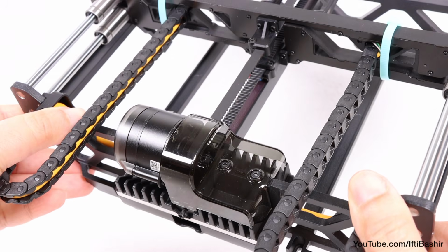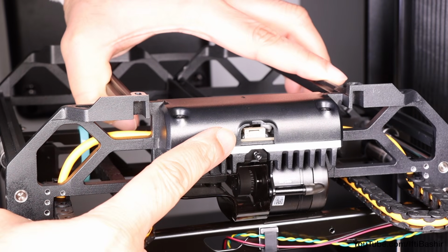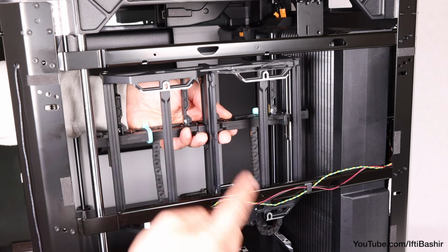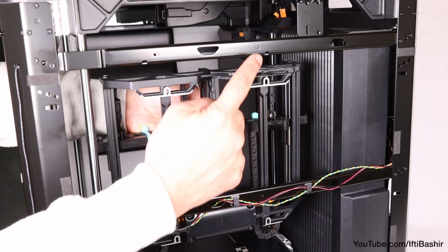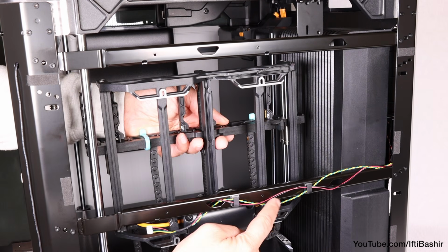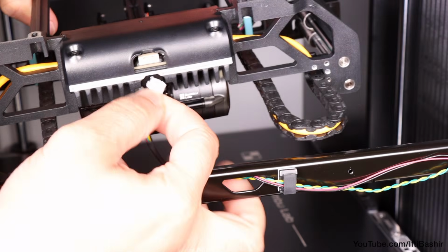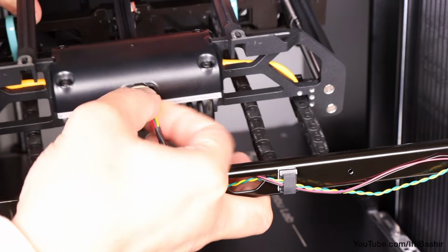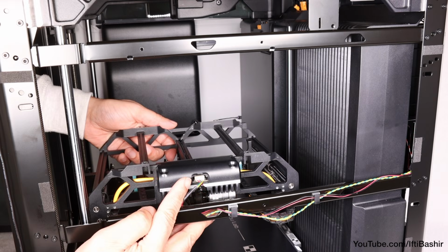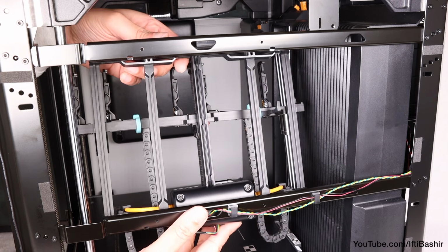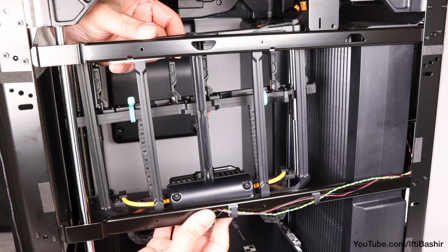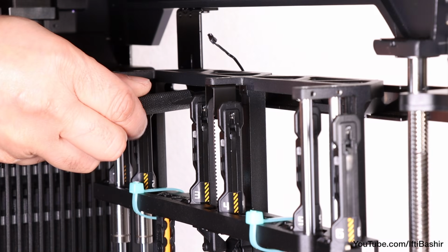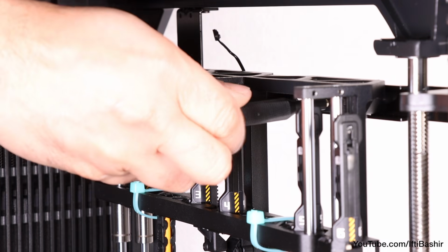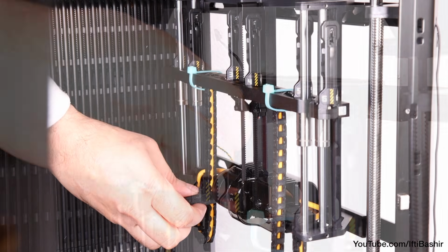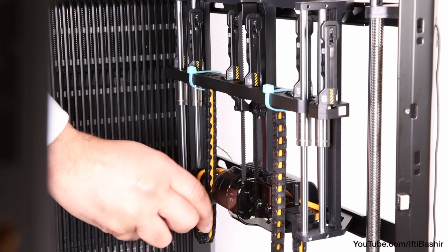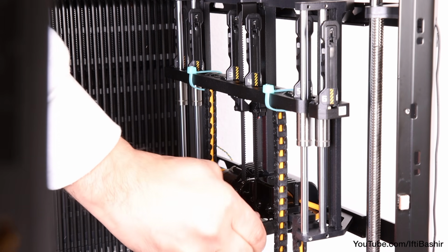Carefully inspect the rack, note the cable connector in the very bottom, along with the 4 mounting locations on the rear side, which will marry up with the 4 screw holes in the 2 beams we previously installed. Okay, so begin by connecting the loose rack connector cable to the bottom of the rack assembly, making sure it is firmly connected and in place, before lining up the rack against its beams. Before securing with 4 M3x6 screws, complete with red thread lock, at both the top and bottom of the beam to ensure even loading without looseness or misalignment.